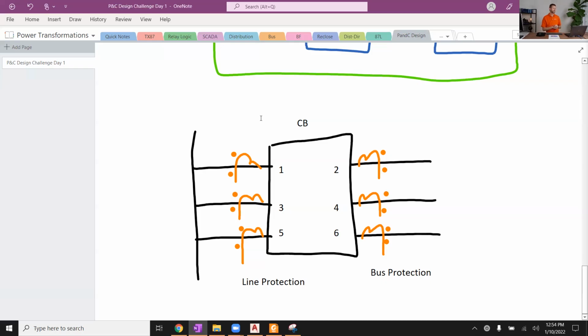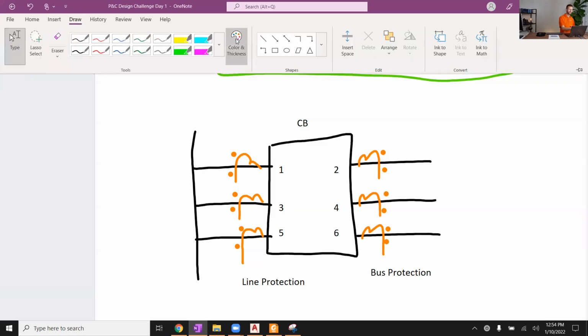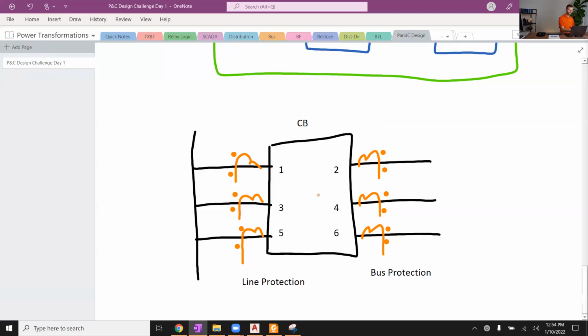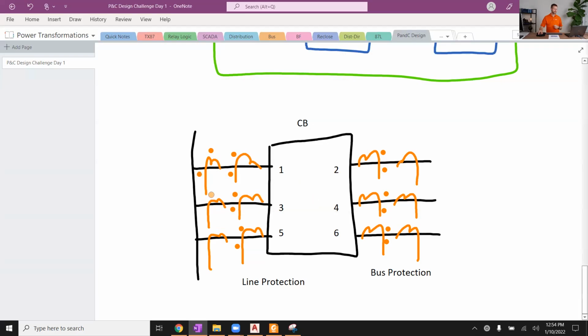And then another thing we sometimes see is double sets of CTs on either bushing. When you're speccing out your breaker, if you have a need for a primary and a backup line relay and a primary and a backup bus relay, then you would have a desire for 2 sets of CTs on either bushing. So this is a total of 6 bushings, right? And this is 2 bushing CTs per bushing. So we're talking about 12 CTs here on this breaker.